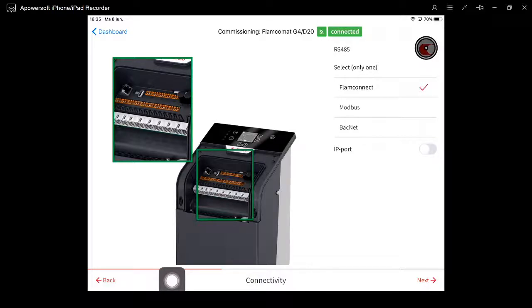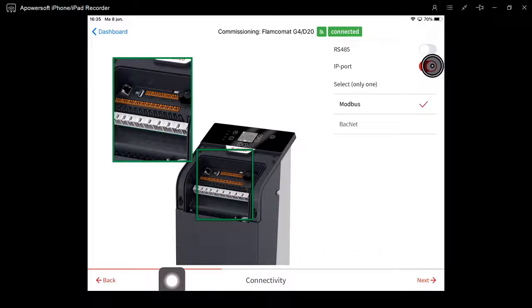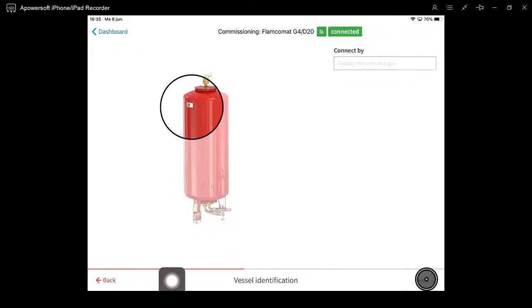Now I can set some connectivity ports. So if we have an RS485 on the Flamcomat G4, where I can say it needs to have Flamconnect. So for a gateway connection, we can choose Modbus or BACnet. I will switch it off, and we have an IP port, and I want to have Modbus on the IP port for external communication with the building management system. So I will press next.